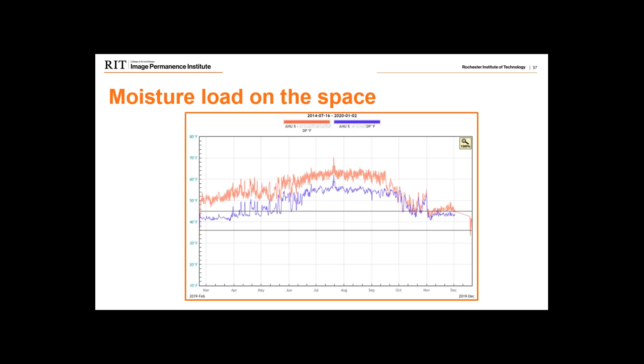In a major scenario like this, we typically don't like to recommend dehumidifiers as a first option. We prefer to keep that as a last resort. But if you're in a situation with such a massive moisture gain, sometimes that's the better option short term, to help reduce humidification until you can address the root cause.